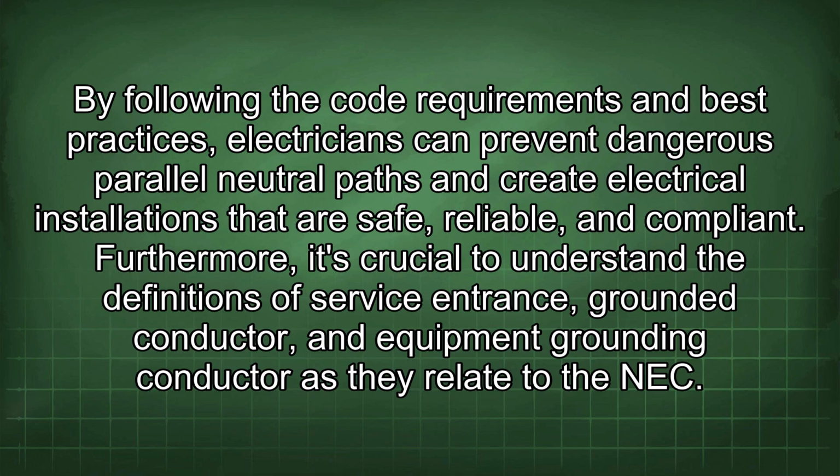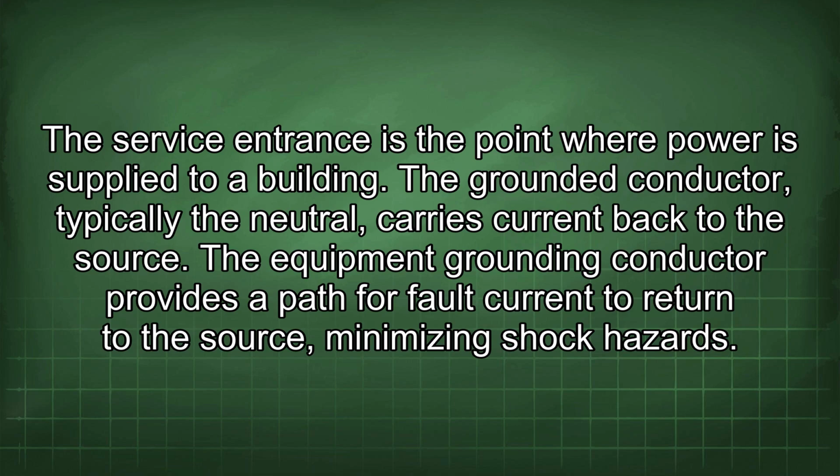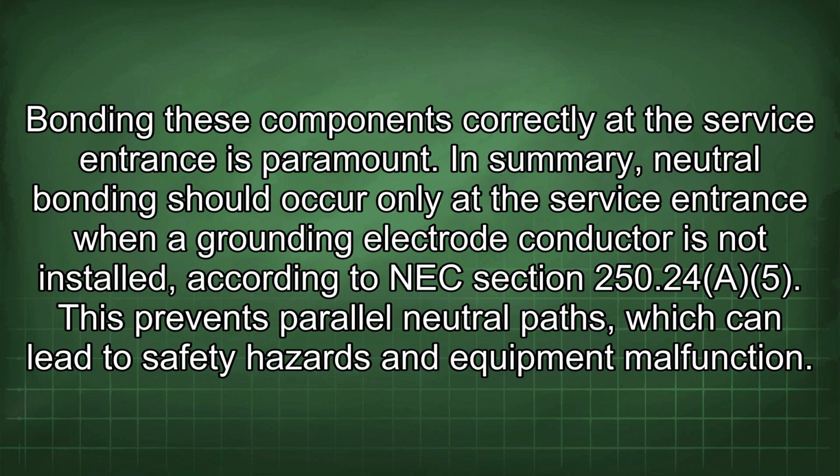Furthermore, it's crucial to understand the definitions of service entrance, grounded conductor, and equipment grounding conductor as they relate to the NEC. The service entrance is the point where power is supplied to a building. The grounded conductor, typically the neutral, carries current back to the source. The equipment grounding conductor provides a path for fault current to return to the source, minimizing shock hazards. Bonding these components correctly at the service entrance is paramount.